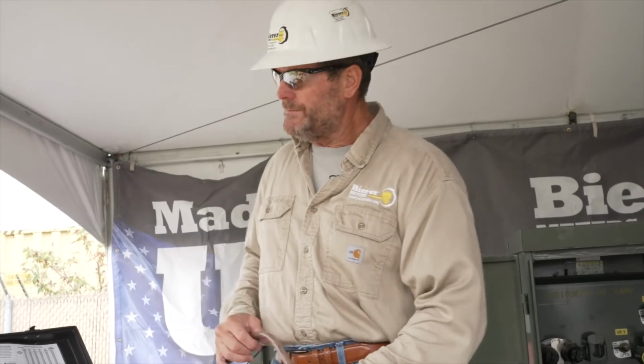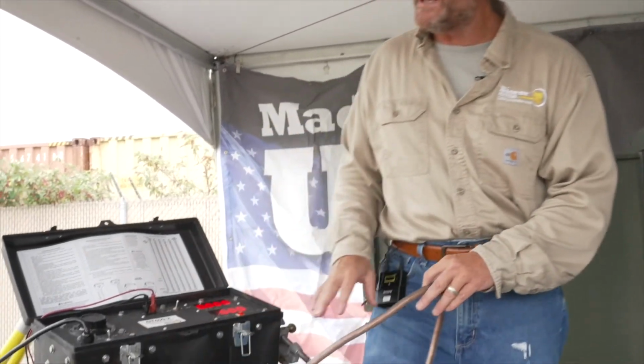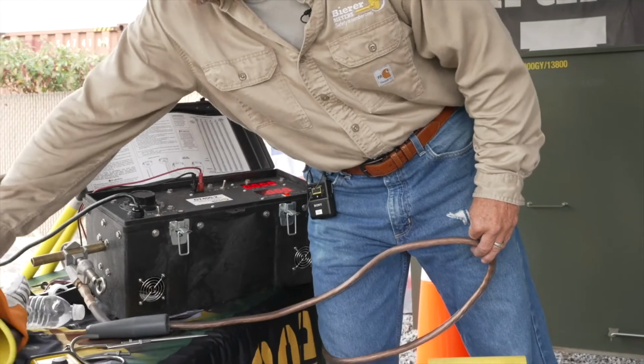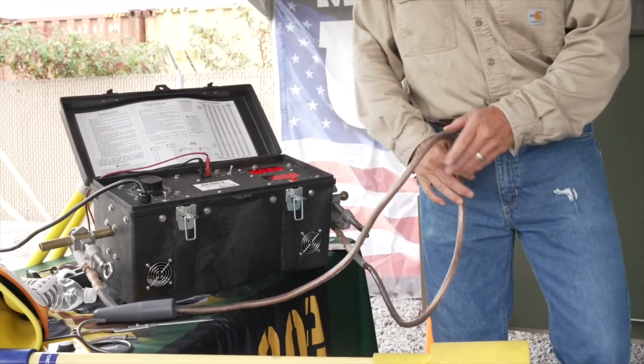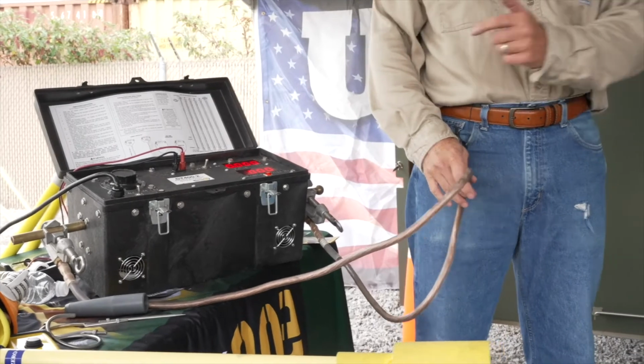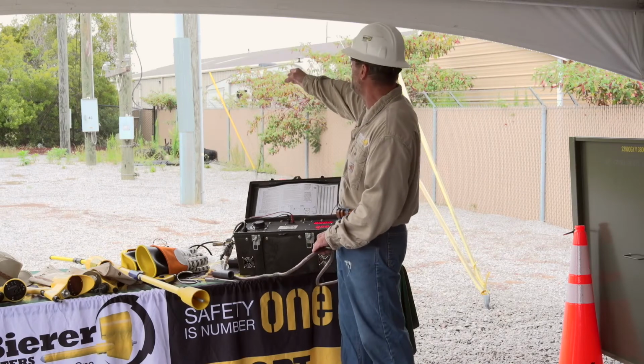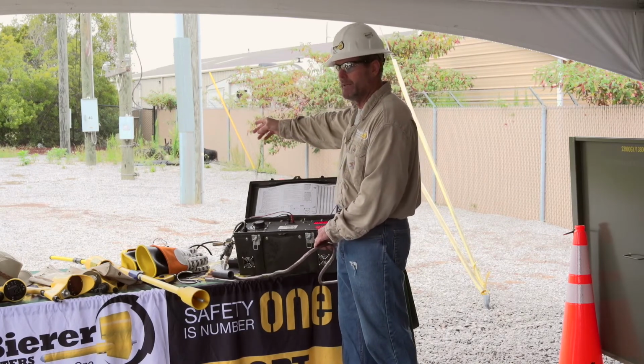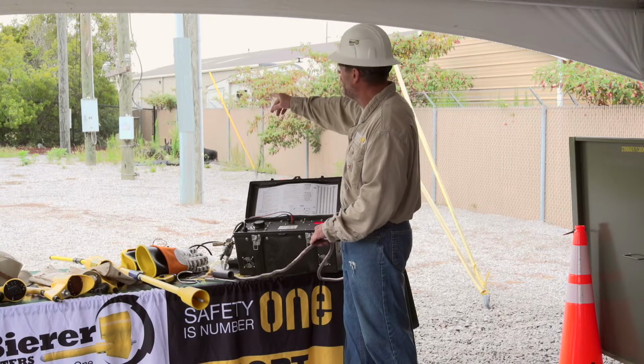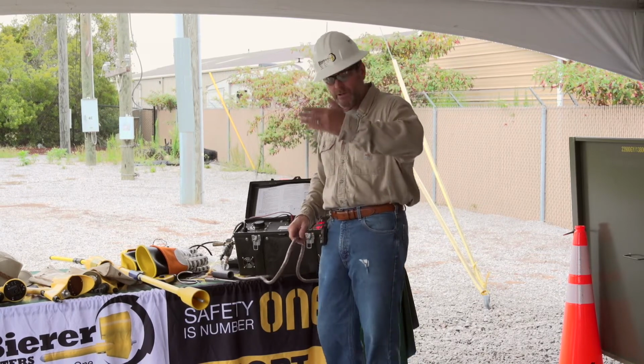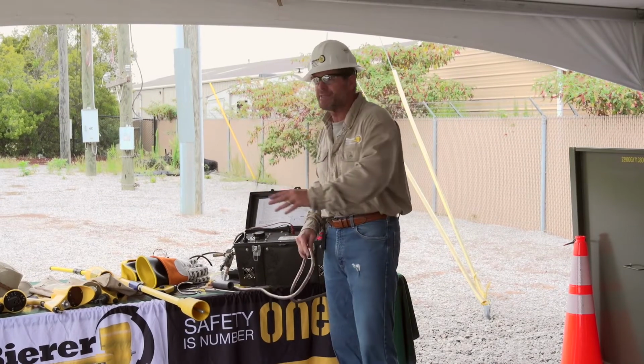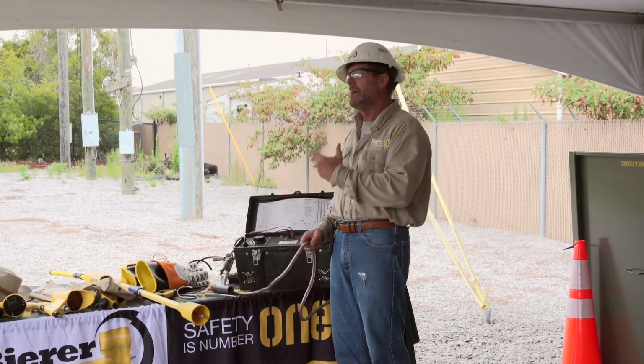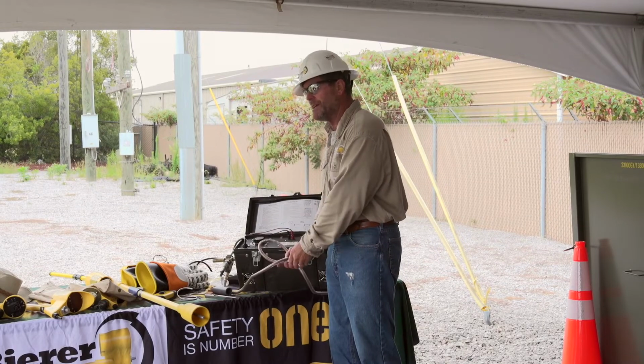Now we're going to electrically test, but before that we want to show you something. We always electrically test with these in a parallel configuration to mimic real-life use out in the field. In real life, when you use your TPGs, you go from point A to point B establishing your EPZ in a straight line. You'll have some droop between conductors, that's fine, but you're not going to have any of your TPGs in a coiled configuration like this.